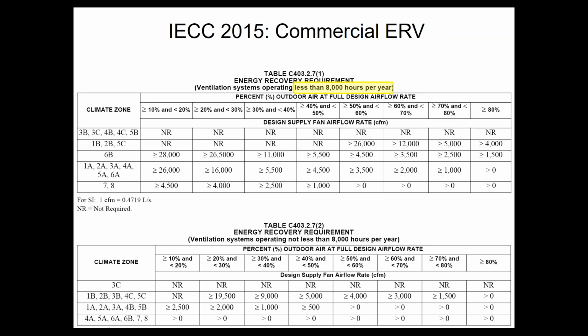We are climate zone 5A and 6A for you guys in northern Illinois and in southern Wisconsin. For you guys in northern Wisconsin, you're climate zone 7, right? The old code, everything to the right of that yellow box, 30% and above, that's exactly the same. Nothing changed there. So if you have a 30% outside air system with 5,500 CFM on your supply fan, you would have had to do the economizer or do the ERV. Now there's another bucket below that for 20% outside air, 16,000 CFM, and 10% outside air on a 26,000 CFM supply system.